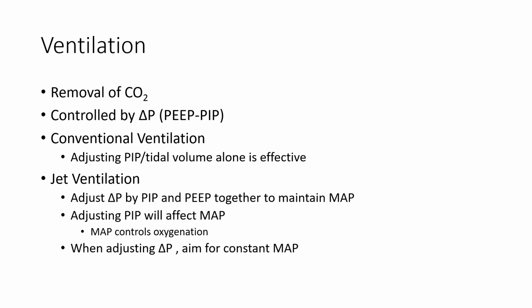Jet ventilation differs from conventional ventilation for carbon dioxide removal. In conventional ventilation, if the carbon dioxide level is too low, the PIP alone could be reduced, or if carbon dioxide is too high, the PIP alone could be increased. During jet ventilation, carbon dioxide levels can be increased by reducing the delta P. Alternatively, carbon dioxide levels can be decreased by increasing the delta P. However, changes to the PIP will result in inadvertent changes in the mean airway pressure.